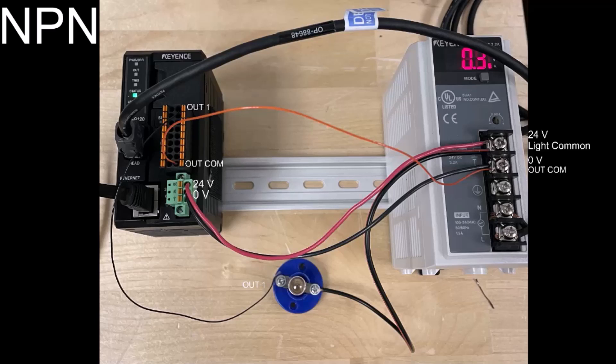Because I want an NPN output, my terminal 18 output common is going to my zero-volt side of the power supply, and my common wire for the light is connected to 24 volts of the power supply.